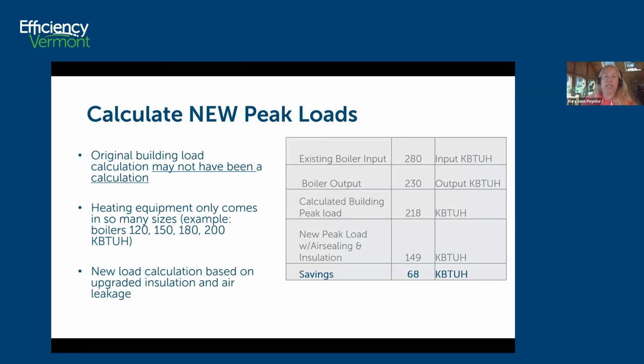So calculating peak loads, this project example that I'm going to go through, these are real numbers, but I'm just using it as an example. So the original building load calculation may not have been an actual calculation. Over the years, people have used rules of thumb on how to come up with the proper size boiler. It could be based on square footage, age of building, all of that goes into picking a boiler size. So in this case, the boiler input was 280 and the boiler output was 230.